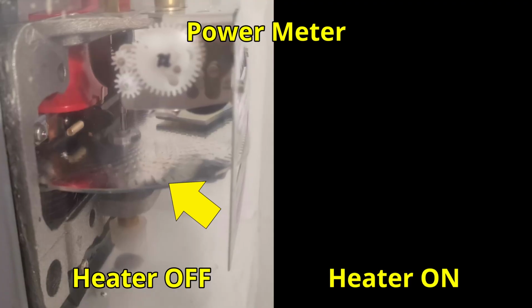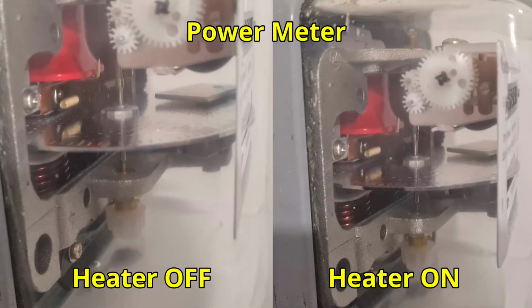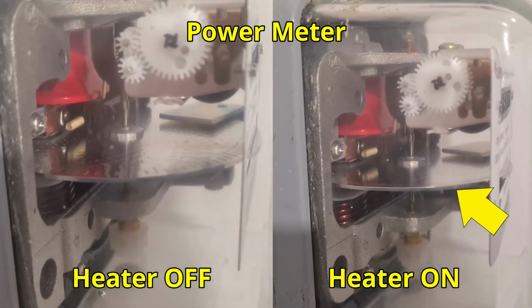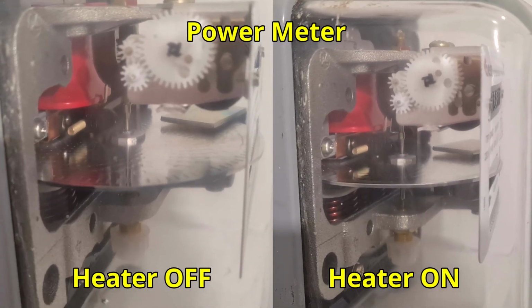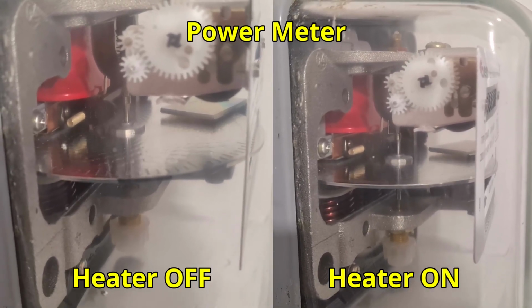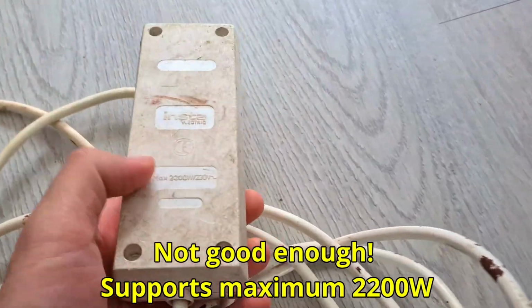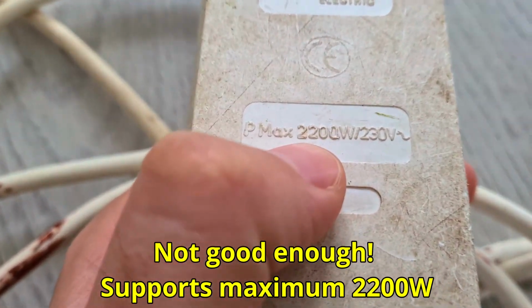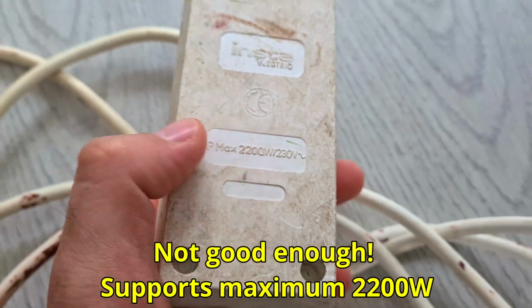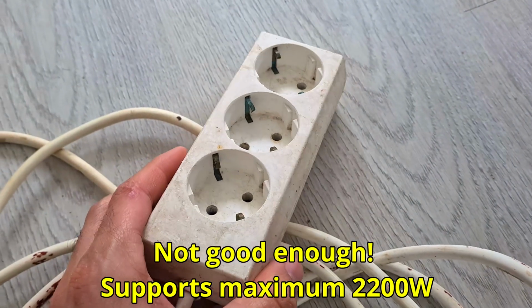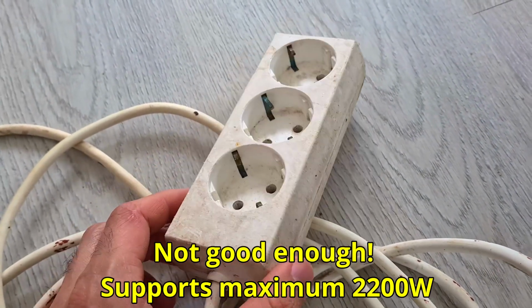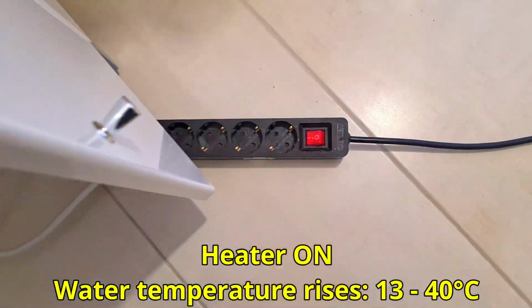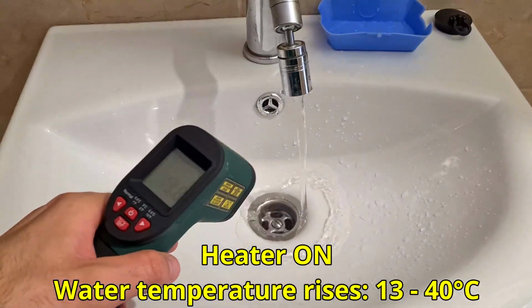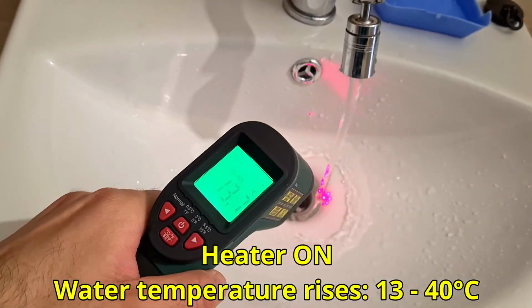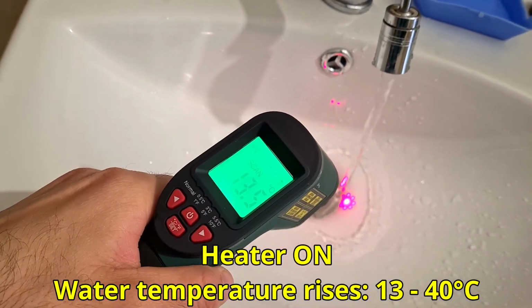So currently the power meter is rotating at this level, and now the heater is on. It's rotating much faster. There's another extension cord, and this one is rated to only 2200 watts. So this should not be used on that heater, which requires at least 1000 watts more. Power it on again. And the temperature should increase.